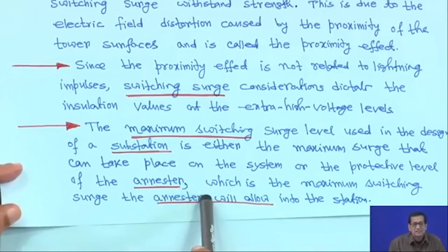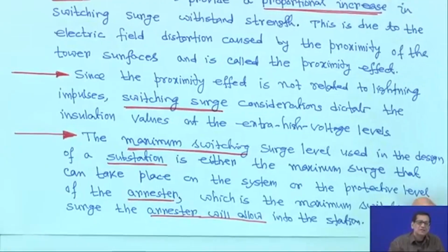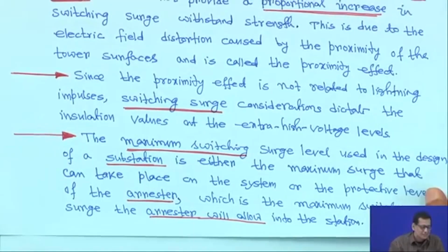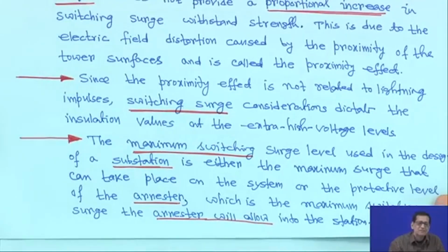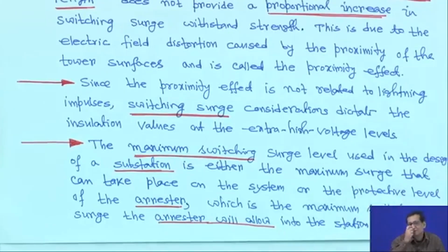So, these are the significant things, but I have seen in a substation that, due to a heavy lightning stroke, even the lightning arrester also failed. This I have seen in the past, right. Somewhere in a substation we found that due to arrester failure, some other equipment also got damaged.